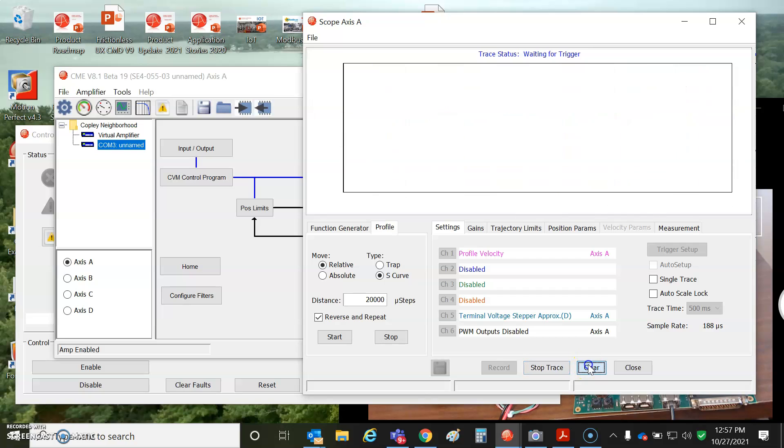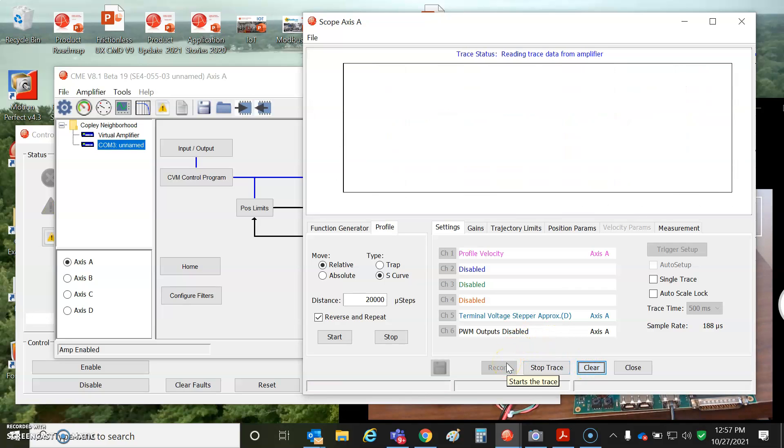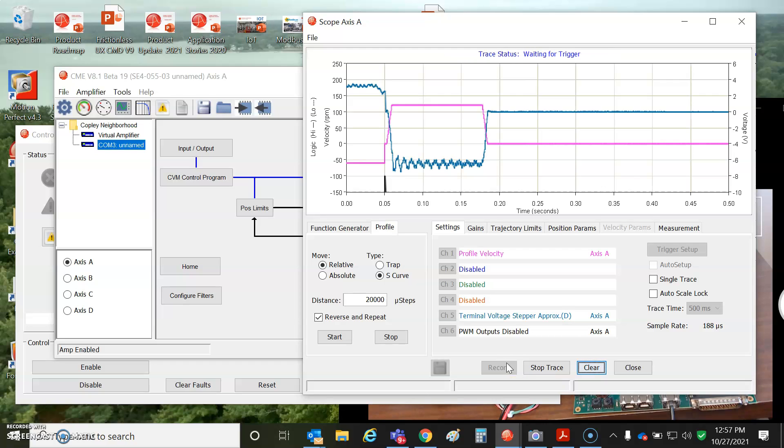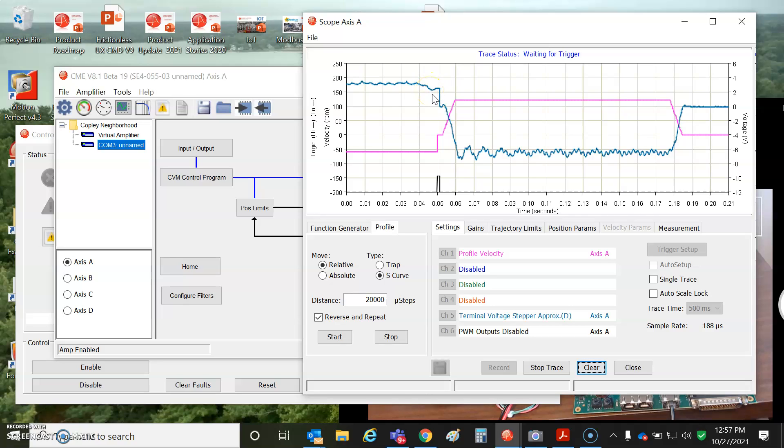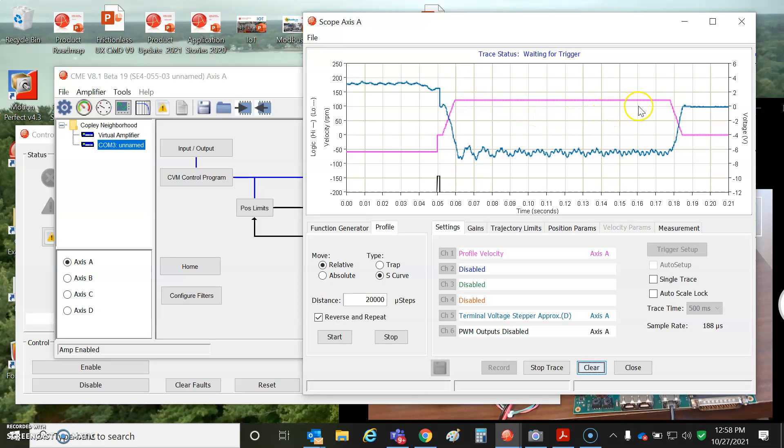I'm going to clear that, hit record. There it goes. Went to the negative, hit the hard stop, disabled. Came back out. And we can see the events here. Just going to zoom in. So I'm cruising along at 60 RPM. I'm going towards the hard stop. I got about three volts here. And then look, the voltage starts to drop. I get close to two volts here. That may be sufficient. And then the drive disables. So I'm in the hard stop. And then after that, come out of the hard stop, move quarter rev, and then stop, and then set the position to zero.